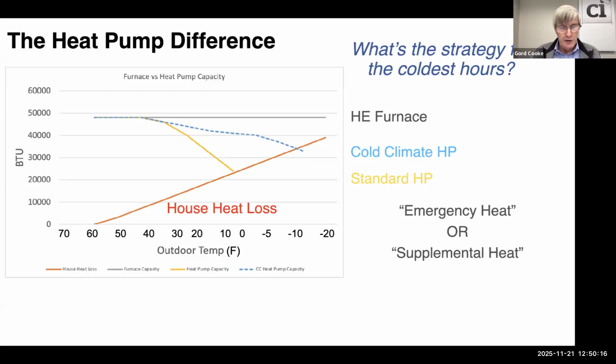The change in today's world is we now have these high performance cold climate heat pumps that continue to operate. They don't shut off. They keep running all the way down to -20, -30. They may not be able to keep up the entire capacity. Notice where it intersects the heat loss line at roughly -10. So if you're going to be colder than -10, you might need a little bit of supplemental heat, but you don't need the 100%. And that's the big difference in today's world. It really allows you to be confident in going all electric because you now have rated appliances right there in the Northeast. Rated appliances do indeed continue to operate at even really cold temperatures.